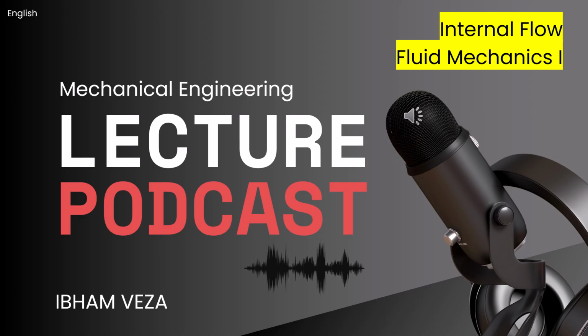Yeah. How do engineers figure out what size pump they actually need? Precisely. A pump adds energy to the fluid. For a typical system, say pumping fluid from a lower reservoir to a higher one, the useful head the pump needs to provide has to be enough to lift the fluid against gravity, that's the elevation difference, plus it has to overcome the total head loss in the entire piping system, all the friction and minor losses. So engineers first determine the system curve.